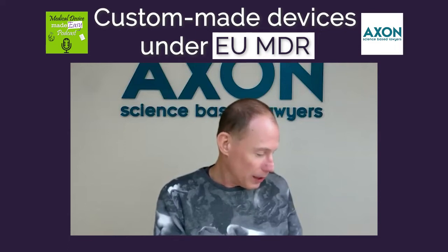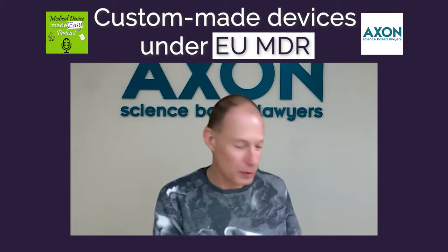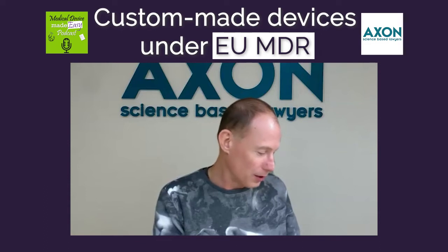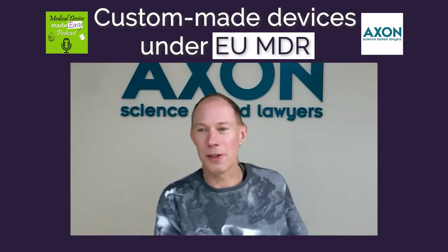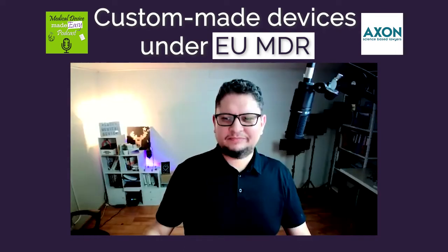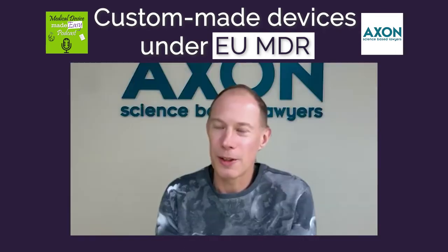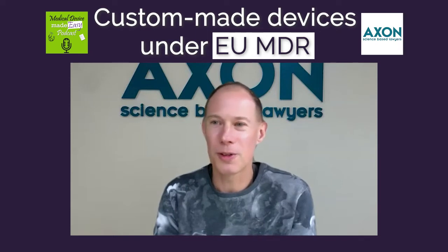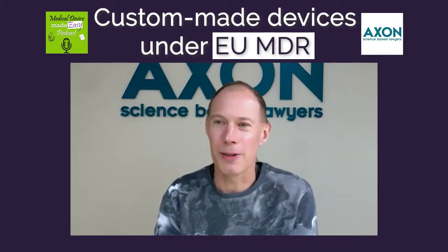So what they do is basically they say, well, you have mass production. They refer in that guidance to an IMDRF document that says you have mass production if the medical device is based on standardized dimensions or design, and it's not designated for a specific particular individual, and it's typically produced in a continuous production run or a homogeneous batch. So what they do actually is that they give a qualitative definition of what is mass produced, just to avoid the discussion about how many.